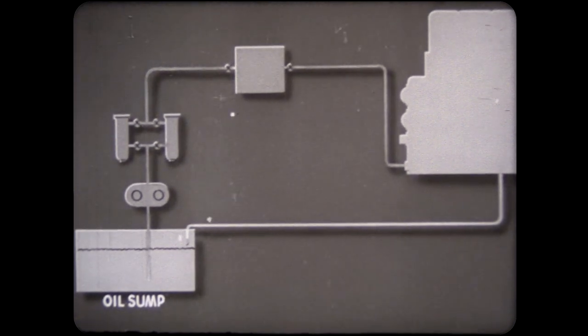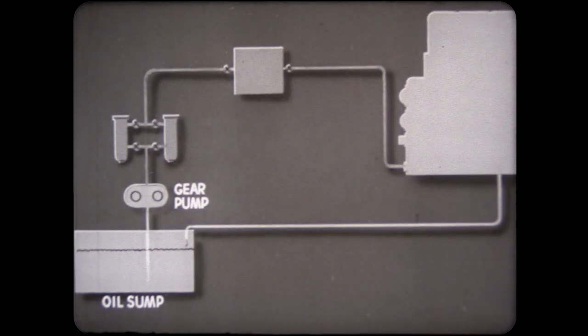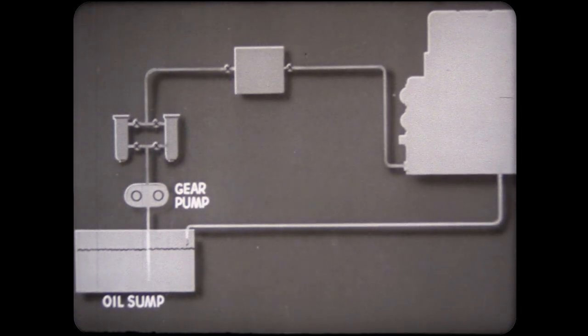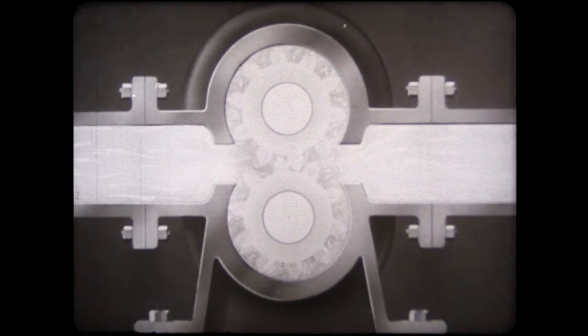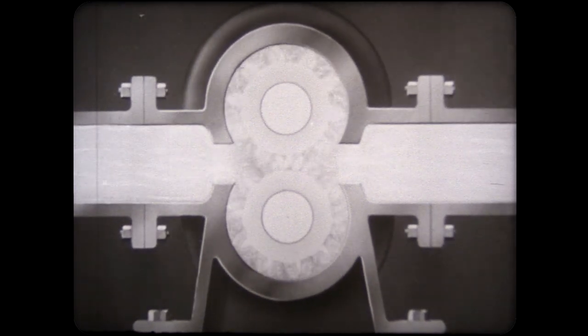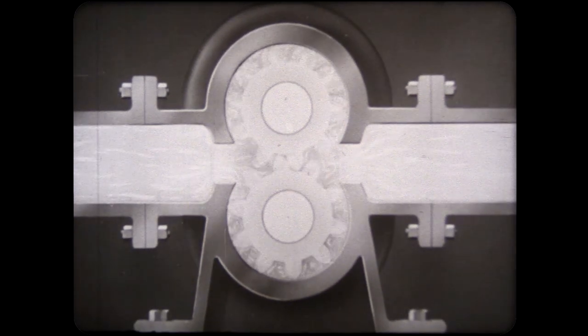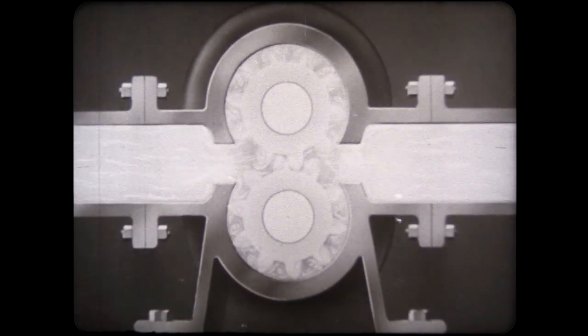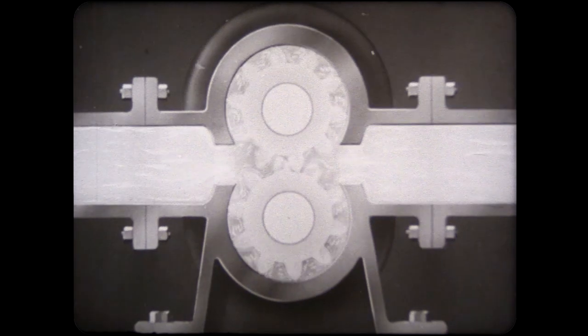The oil is drawn from this tank by a pump, usually a gear pump of the positive displacement type. The oil entering the suction side is trapped between the gear teeth and the pump housing. The rotating gears discharge the trapped oil at sufficient pressure to force it through the system.